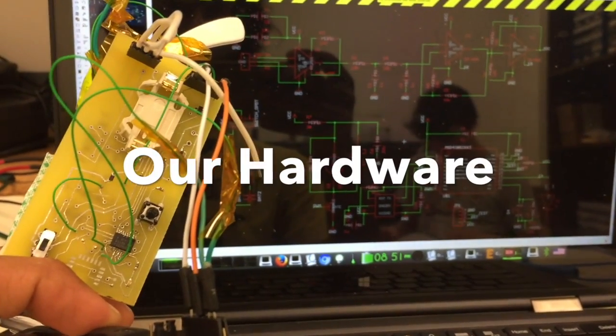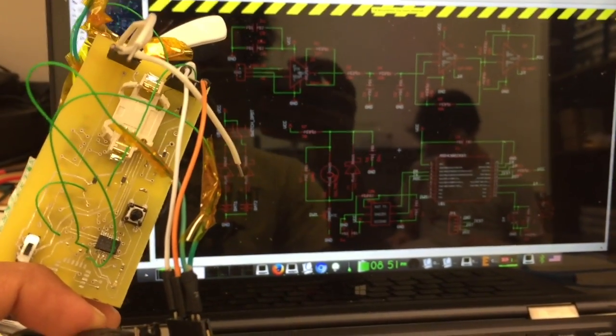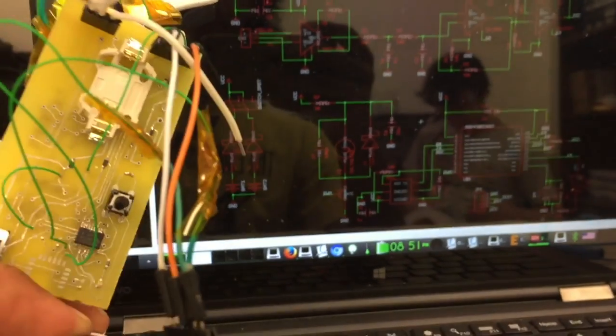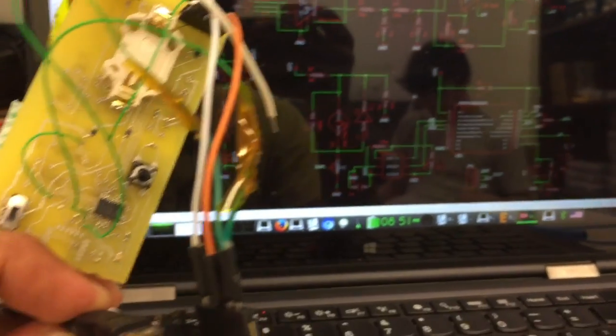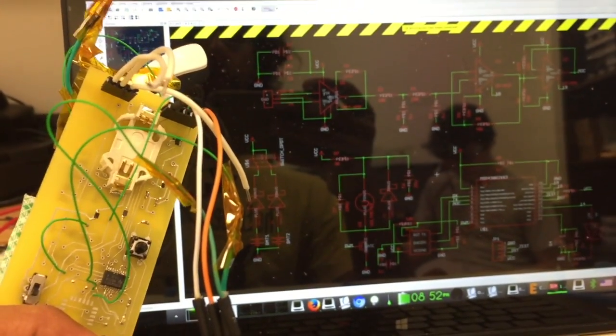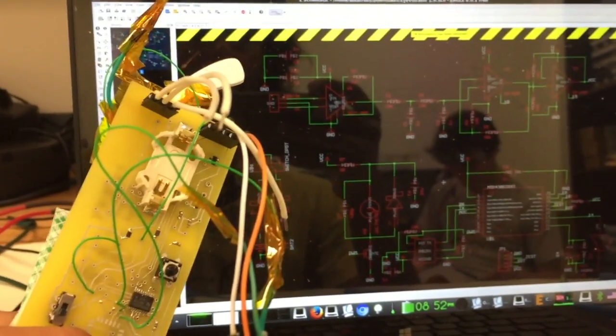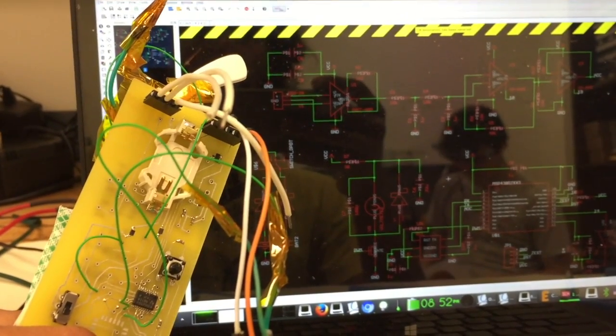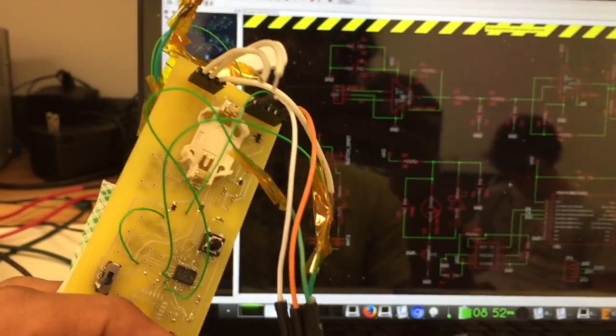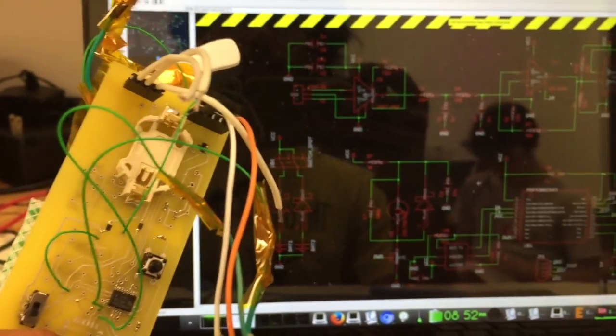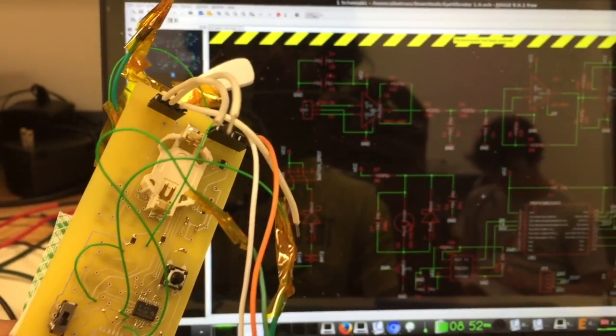The input to our system is a small signal from across the eyes, measuring between 0.1 to 1 millivolt. That signal is amplified by about 500 times through an instrumentation amp. We selected an amp that could amplify signals which are very close to zero on the negative side without actually requiring a negative supply voltage, thereby reducing the need to create two power supply lines.